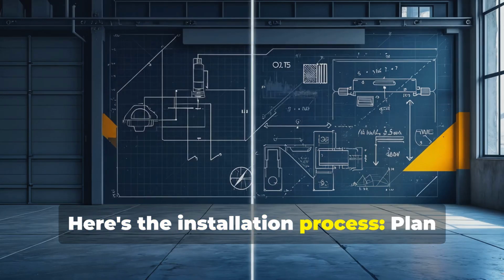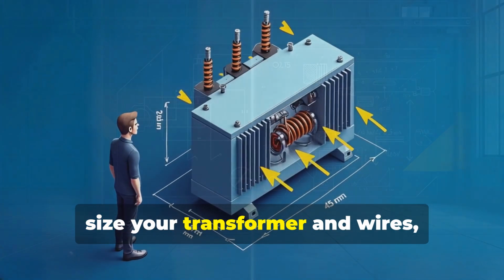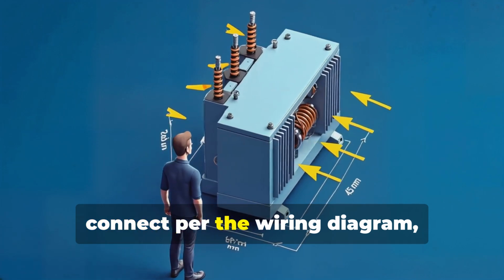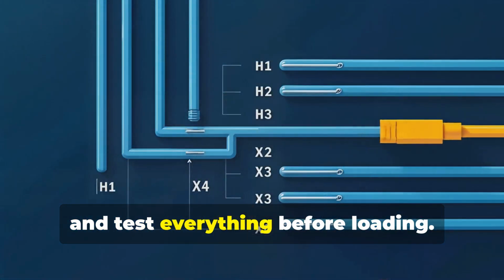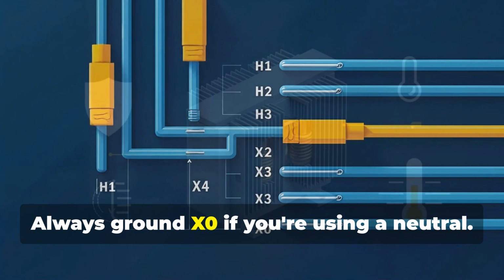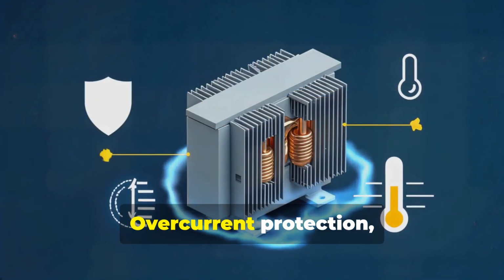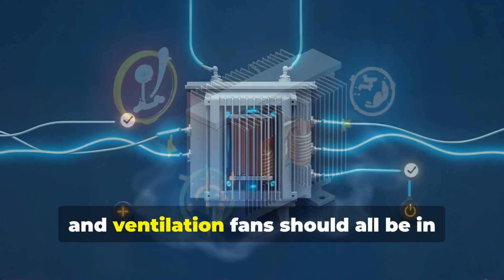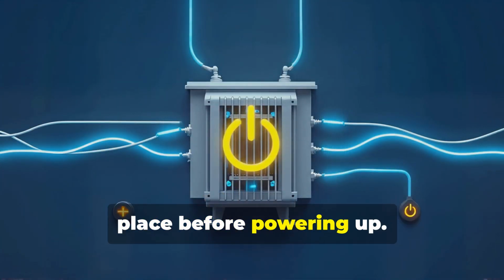Here's the installation process. Plan your setup, size your transformer and wires, connect per the wiring diagram, and test everything before loading. Always ground X0 if you're using a neutral. Overcurrent protection, temperature sensors, and ventilation fans should all be in place before powering up.